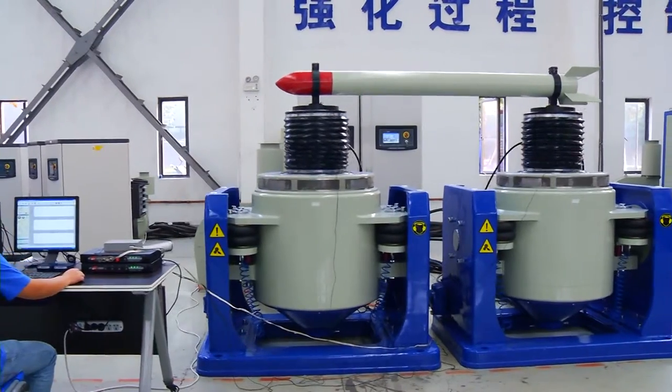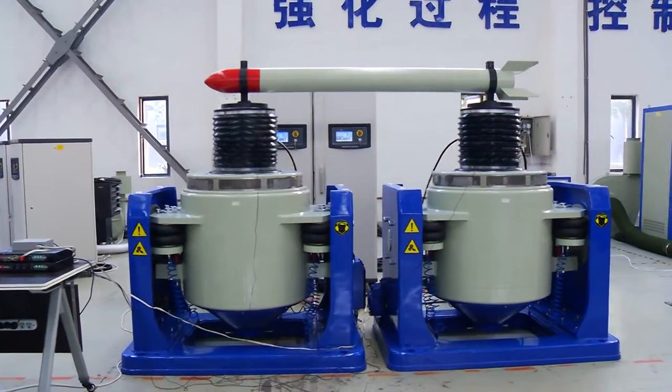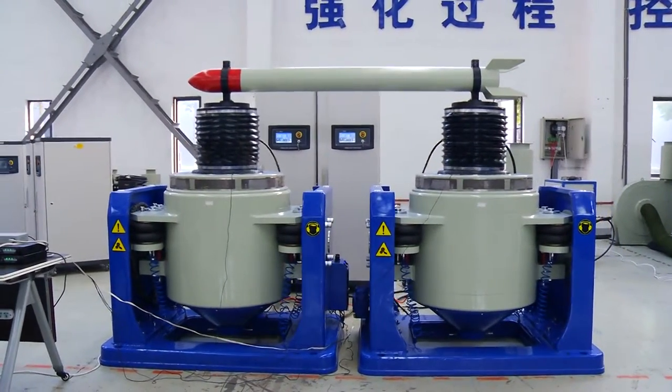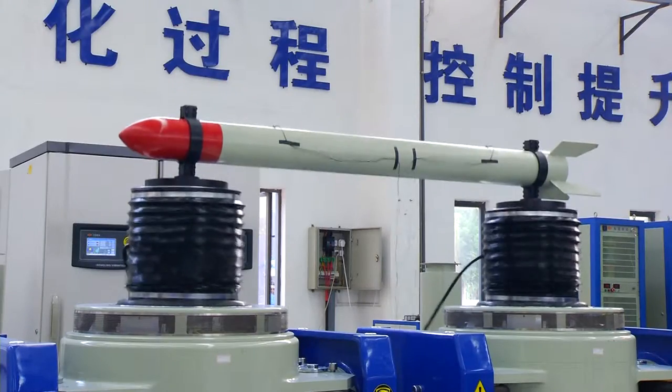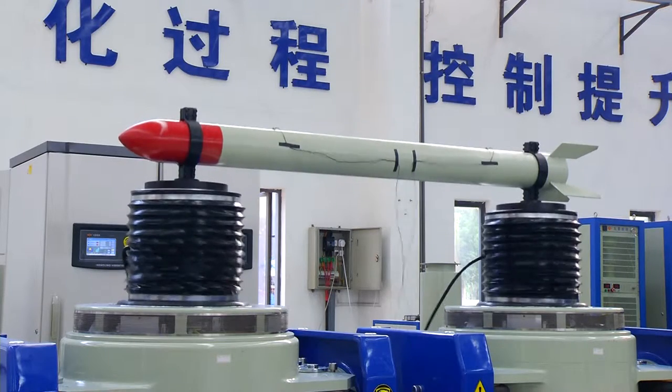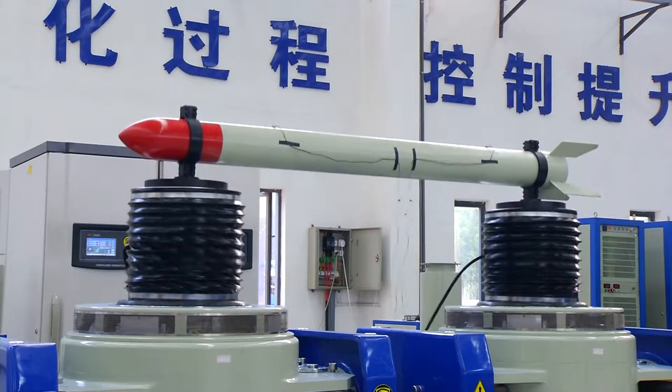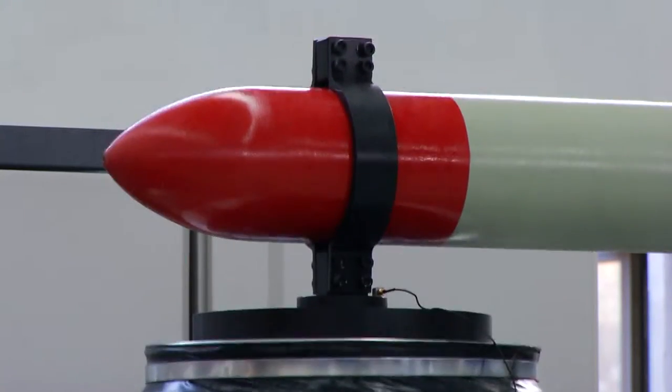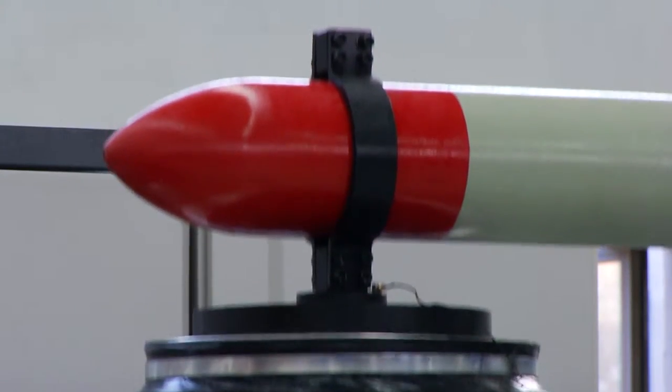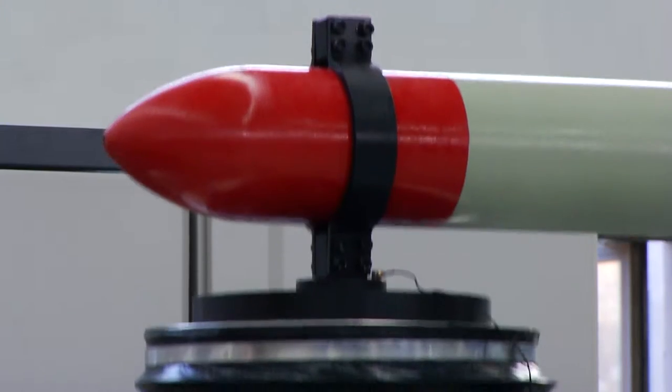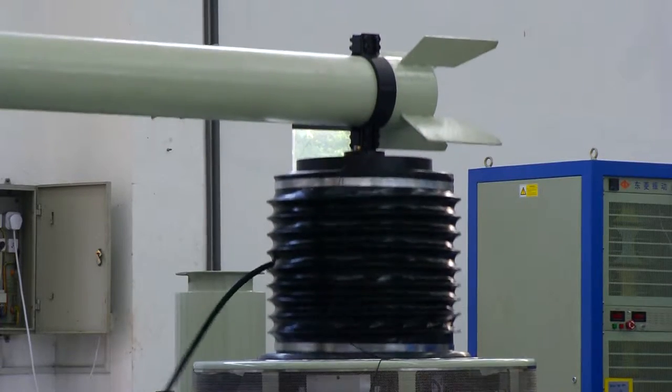It can make the vibration condition more close to actual environment. This system uses hydrostatic spherical coupling for angle compensation, which is Dongling's product with completely proprietary intellectual property rights. It can well achieve synchronous and asynchronous tests.